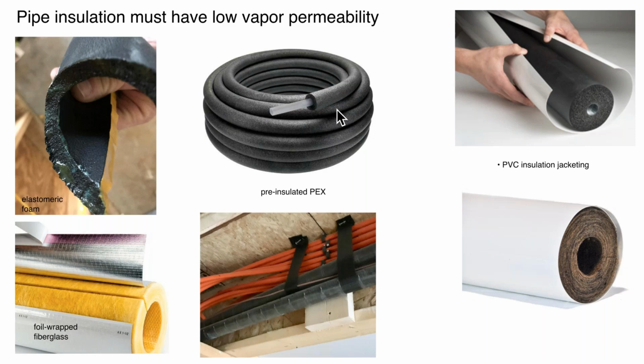There are other materials like foil wrap fiberglass. What you don't want to do is put a material on here that lacks a vapor barrier. The vapor migration will be from the outside towards the pipe, and if that was just the fiberglass material, it's going to get saturated very quickly with condensate.